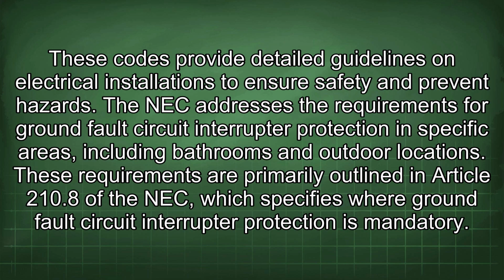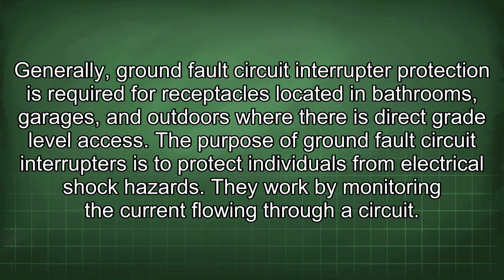The NEC addresses the requirements for ground fault circuit interrupter protection in specific areas, including bathrooms and outdoor locations. These requirements are primarily outlined in Article 210.8 of the NEC, which specifies where ground fault circuit interrupter protection is mandatory. Generally, ground fault circuit interrupter protection is required for receptacles located in bathrooms, garages, and outdoors where there is direct grade level access. The purpose of ground fault circuit interrupters is to protect individuals from electrical shock hazards.